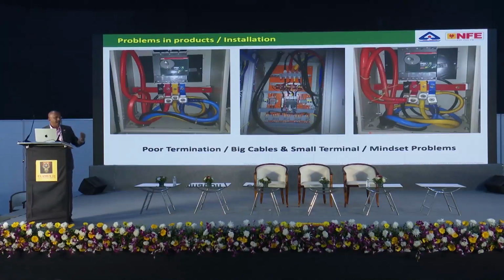Similarly, another subject, I'm sure some of you may know this kind of picture. This is a bus bar, the tap-off box in a bus bar. Terminals are so small and we use large size wires. Then we have a habit of twisting the wire inside the box. As a result, what happens? This installation, which is supposed to work for 25-30 years without trouble, will not even work for 2 years. It will unnecessarily heat up. Then what do we do? We take thermography and try to tighten every joint. This is against electrical safety. This is not electrical safety.